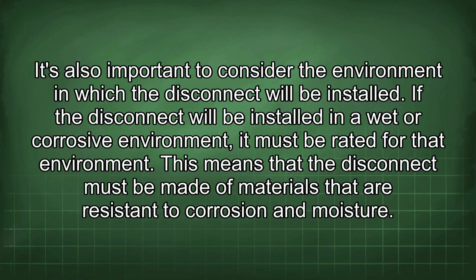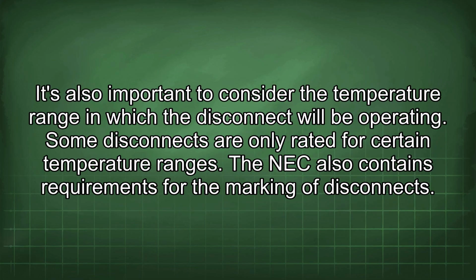It's also important to consider the environment in which the disconnect will be installed. If the disconnect will be installed in a wet or corrosive environment, it must be rated for that environment. This means that the disconnect must be made of materials that are resistant to corrosion and moisture. It's also important to consider the temperature range in which the disconnect will be operating. Some disconnects are only rated for certain temperature ranges.